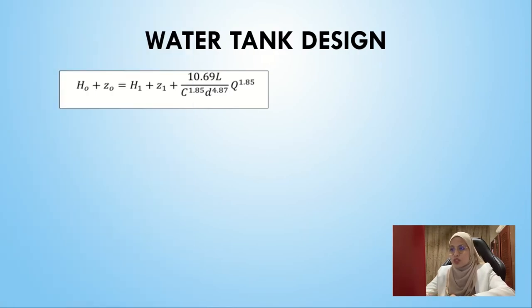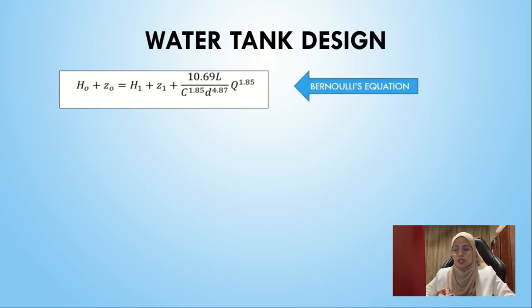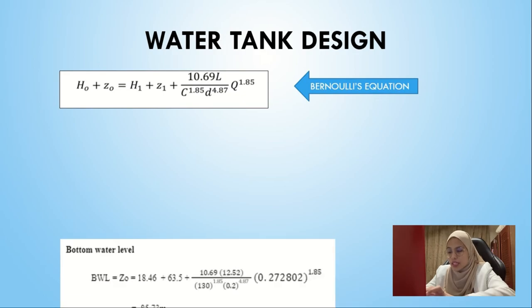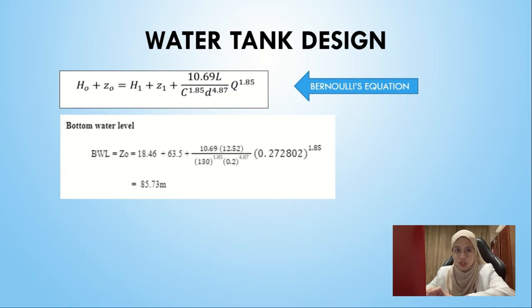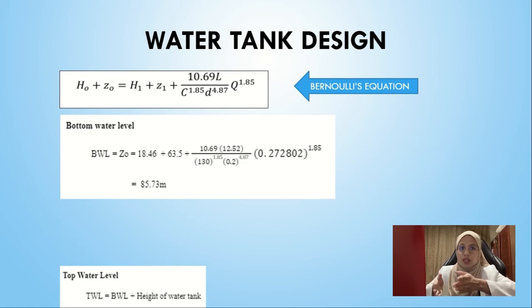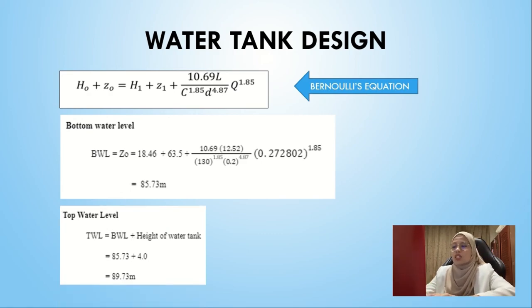We proceed to the water tank design using Bernoulli's equation to calculate the bottom water level. Data is obtained from previous calculations and ePanet. We get 85.73 meters for the bottom water level, measured from the elevation. The top water level is calculated by adding the bottom water level to the proposed tank height of 4 meters, giving a top water level of 89.73 meters.